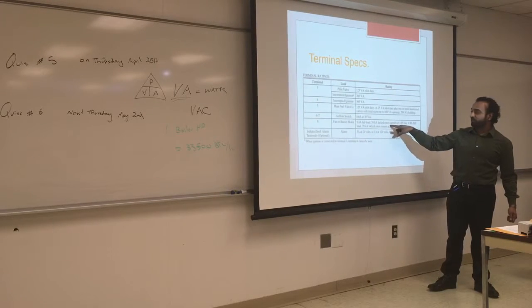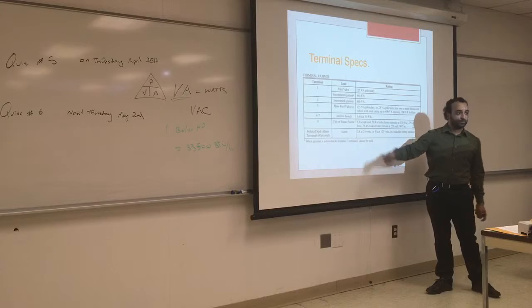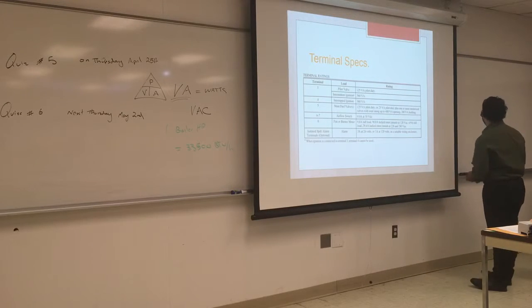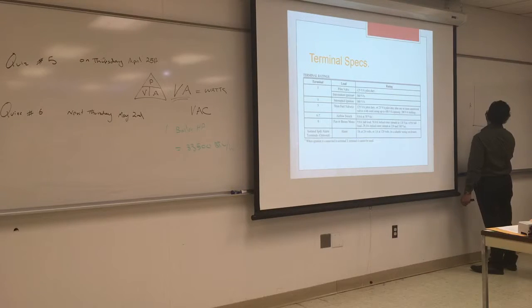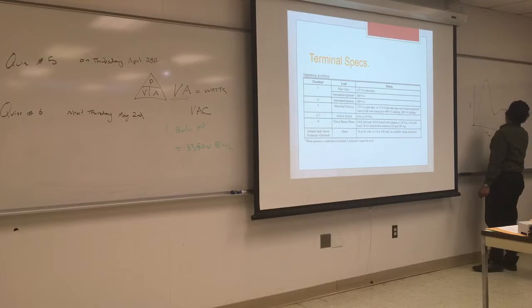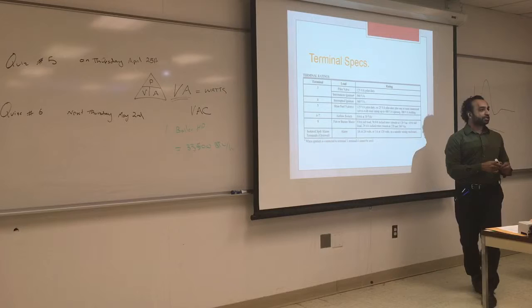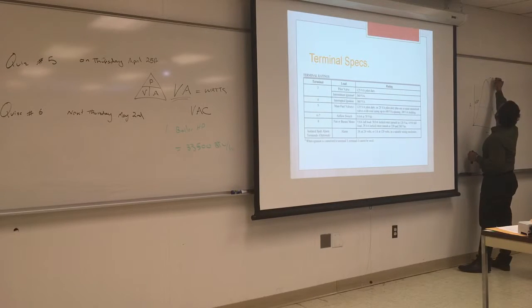So you should have a really good circuit breaker for that, because if it's locked, it's going to be 58 amps until it moves again, and full load is when it's running normally. So you always have a spike when you start the motor from 0. And it's neutral. So the full load is going to be here. That's going to be 9.8 amps. And this is 58 point what?